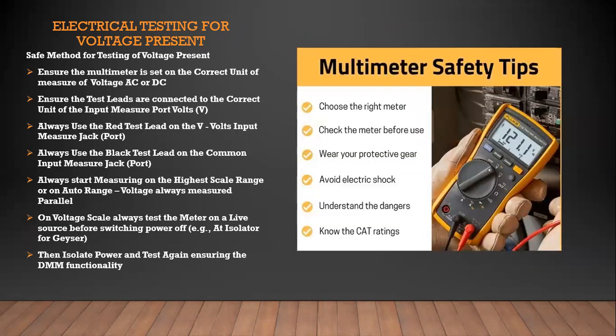If we look at the next slide, electrical testing for voltage present, I should actually show you how to test on the geyser, how to test if there's voltage after you've isolated the geyser for maintenance. Make sure how to do it properly. We all know water heaters are installed, most of them in ceiling voids or up in the roof where there's a restricted confined space. Should you get electrocuted there, it's not a nice place to get, because you're cramped up, you're sitting in there, there's not space, it could become fatal. So test is the most important thing, how to do it correctly and how to do it safely.